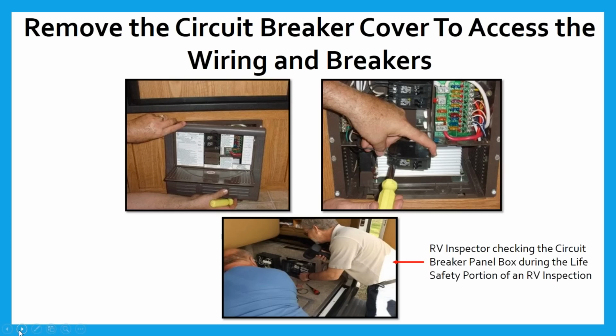Neither can you, so you need to get in there and do some inspection. Now, in this bottom picture, this gentleman right here is one of our inspectors, and he's doing quite well for himself. His name is Dave. Dave is doing the inspection on a panel box for an RV inspection, because this is one of the things we ask the RV inspector to do—a life safety test, because this is serious. They want to get inside that panel, take pictures of it. See, he's got his flashlight, he's looking at it, and he'll write that up in a report. If he finds some wiring that's loose, he's going to make a notation—he's not going to tighten it up, he's going to make a notation, because they'll need to get somebody in there. Or if he finds wiring that's discolored, he's going to make a notation, so that way somebody will know. It's got to alert the people: hey, you've got a potential problem here.